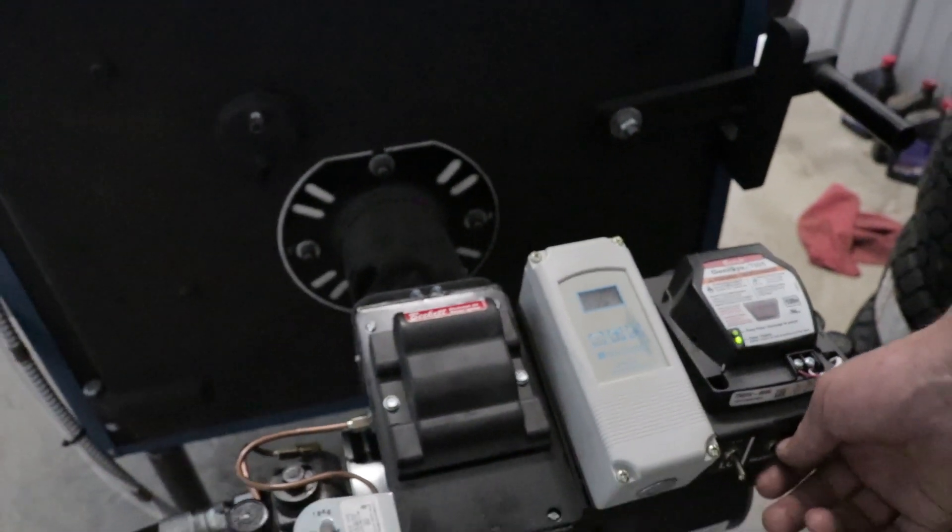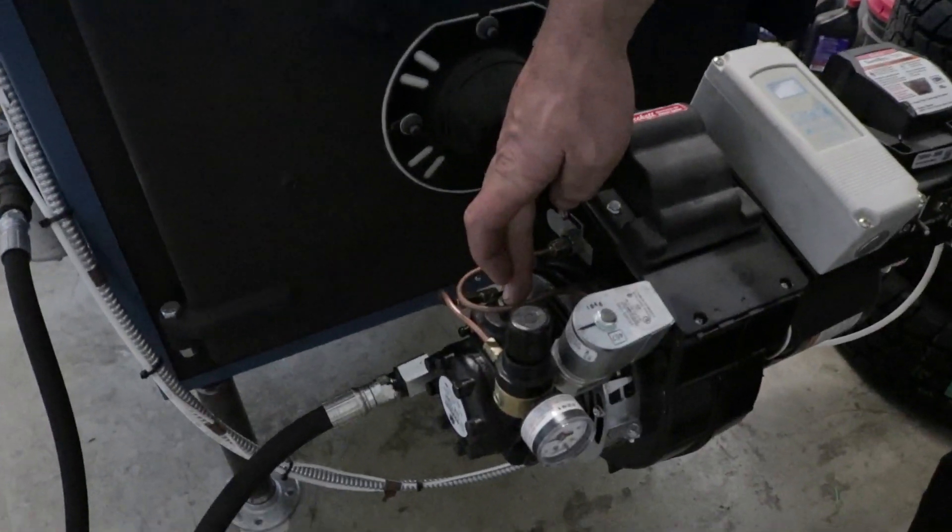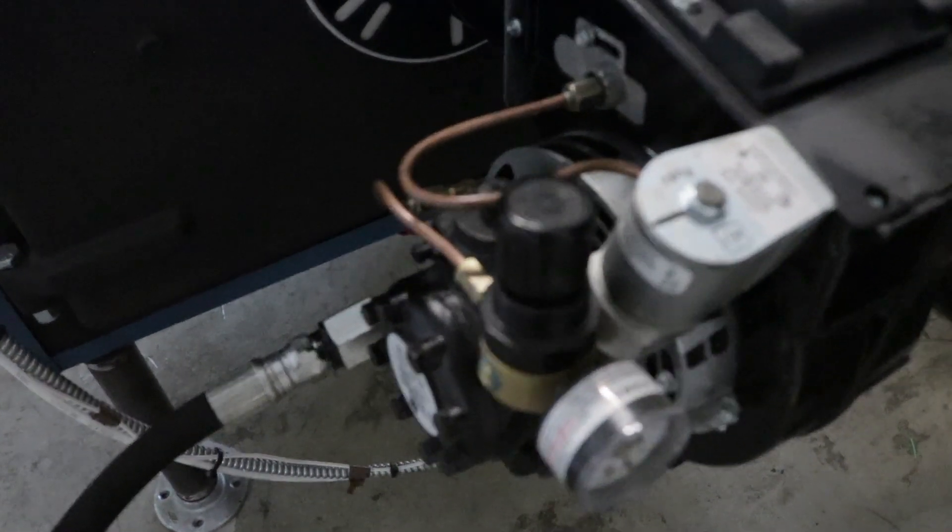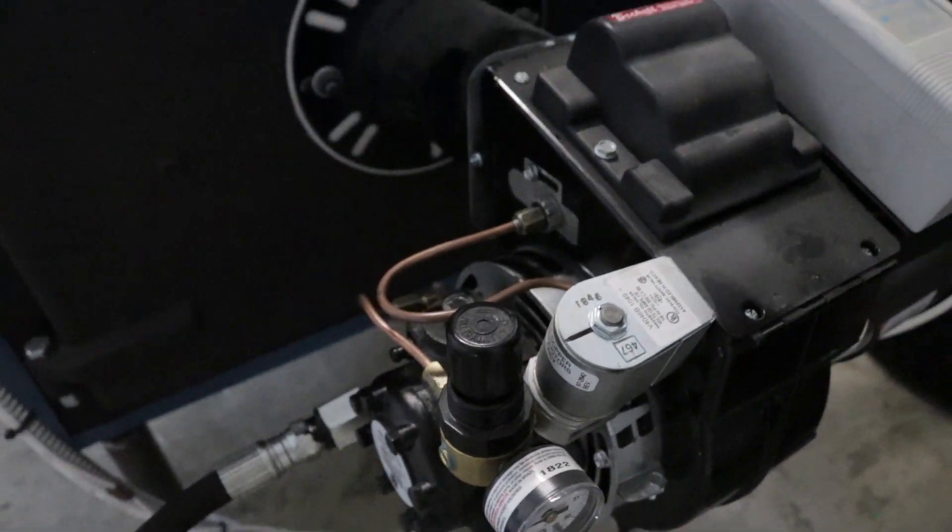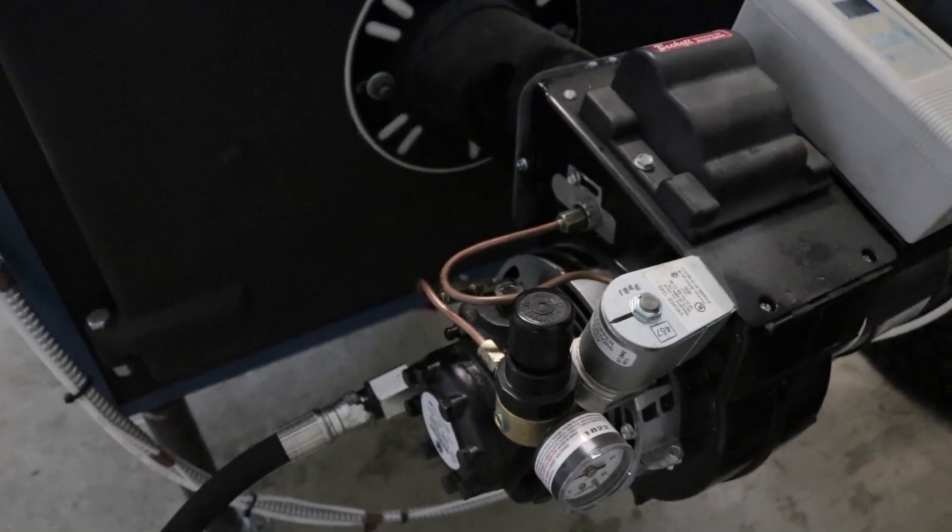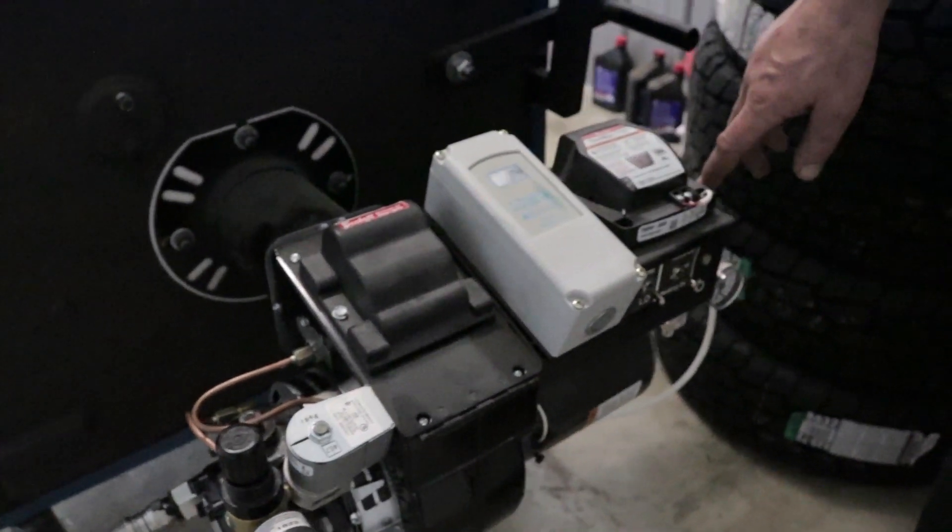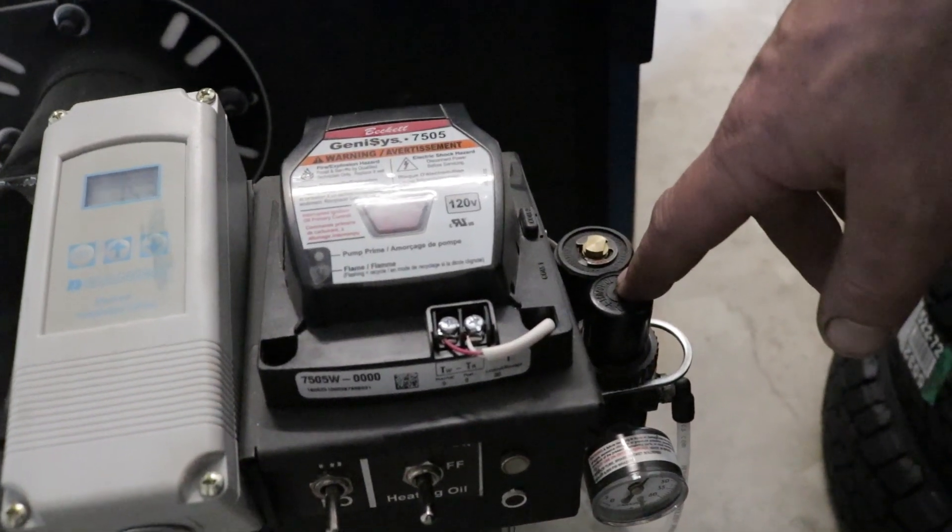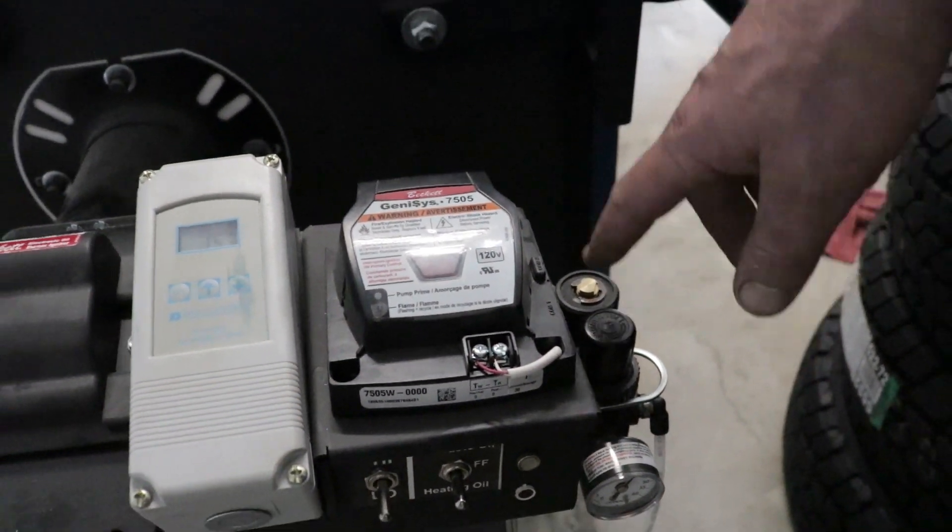We have a high viscosity pump that's designed specifically for waste oil. We also have compressed air. This is a regulator that regulates the oil flow going through the nozzle and the burner, and this is a compressed air regulator that regulates the compressed air.